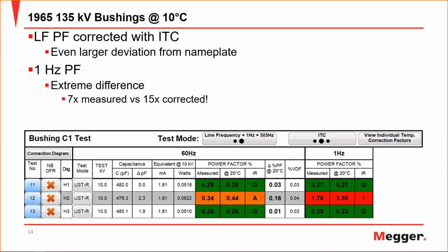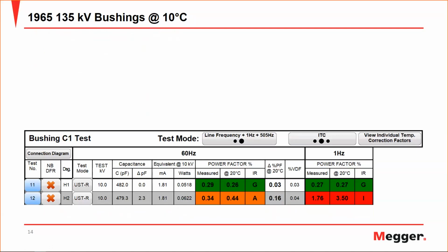So this is a further confirmation of those poor line frequency measurements. But again, all we're doing with the 1 Hertz is pointing you in to look at a particular bushing that may have a problem compared to its sister bushings. But the 1 Hertz cannot tell you the exact state of that particular bushing or asset. So what you need to do is bring out the IDAX, and this will give you the definitive answer.